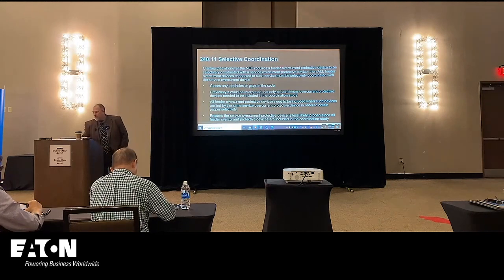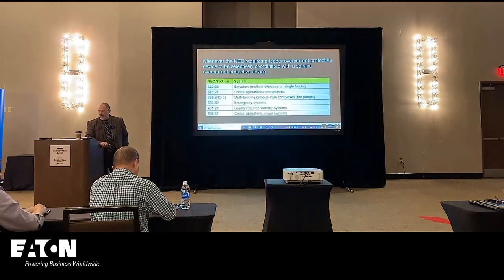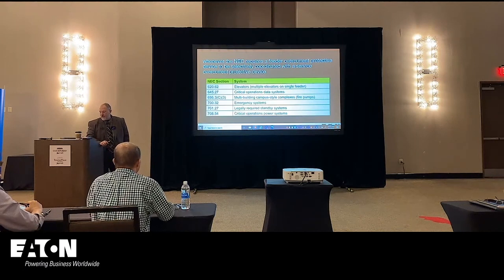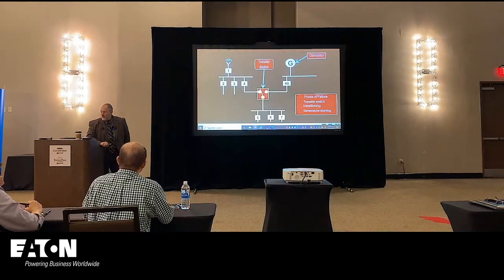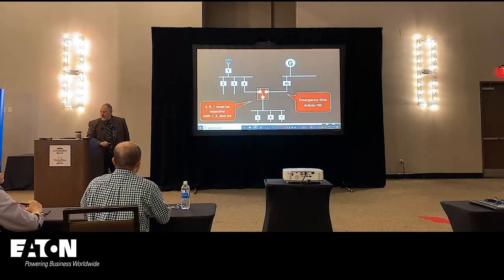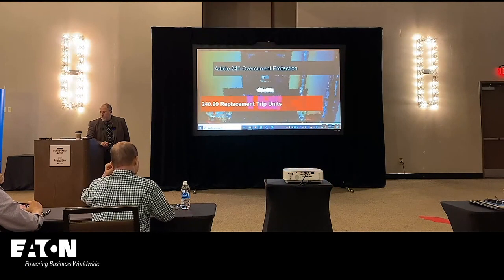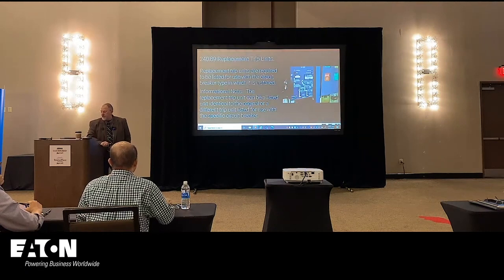Anywhere that the feeder overcurrent protected devices need to be selectively coordinated with a service, basically anywhere you're feeding these types of systems, 620, 645, et cetera, you need to selectively coordinate those devices. Make sense? And that's it. And then the replacement trip units have to be listed.